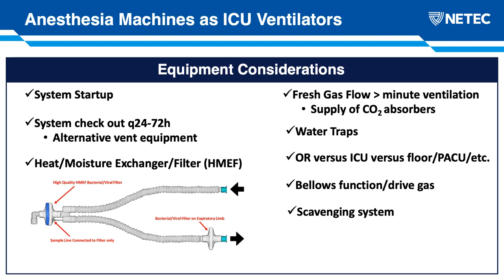And when thinking through where best to stand up this kind of activity, one has to think through the pros and cons of all of our different physical spaces across the hospital. So we know that in the OR, all of the necessary connections are present: the gas lines, the scavenging system, suction, etc. But it's often not practical to go OR to OR, though it has been done, especially in places like New York City. Other centers look at deploying these into an ICU environment, and one simply needs to make sure that you partner with your facilities team to investigate the availability of both the supply gases and the suction necessary for waste gas scavenging.